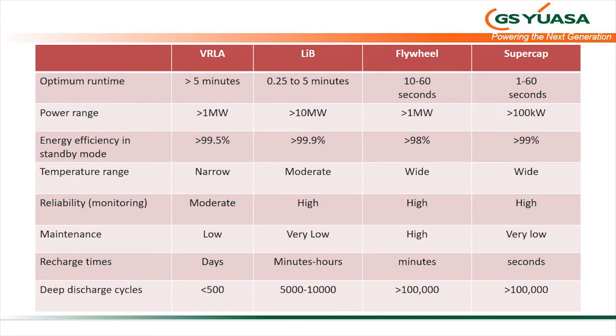And then maintenance, low for the batteries, whereas flywheels, you have to replace the bearings every few years. High cost, very skilled work. And recharge times, seconds or minutes for flywheels. We're talking a few minutes to an hour or so for lithium ion, but days to get lead acid back up.